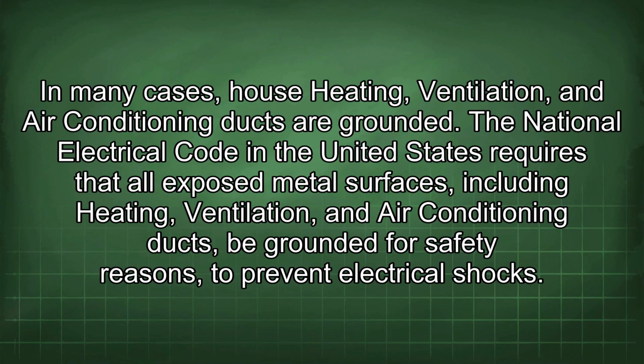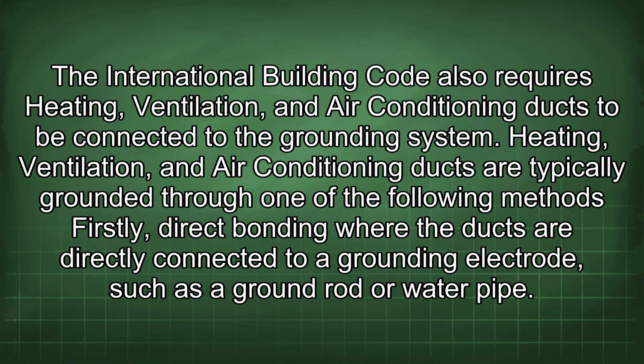In many cases, house heating, ventilation, and air conditioning ducts are grounded. The National Electrical Code in the United States requires that all exposed metal surfaces, including heating, ventilation, and air conditioning ducts, be grounded for safety reasons to prevent electrical shocks. The International Building Code also requires heating, ventilation, and air conditioning ducts to be connected to the grounding system. Heating, ventilation, and air conditioning ducts are typically grounded through one of the following methods.